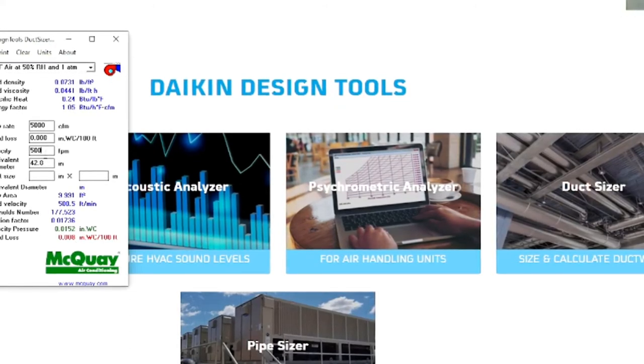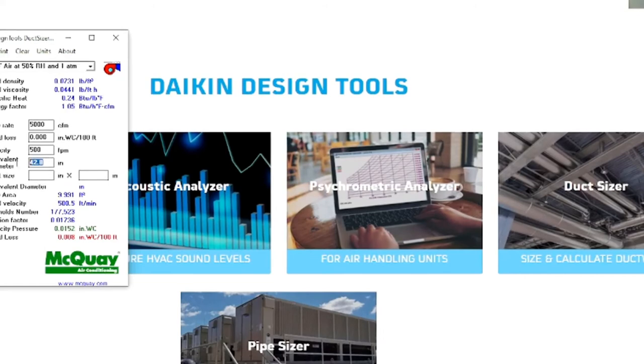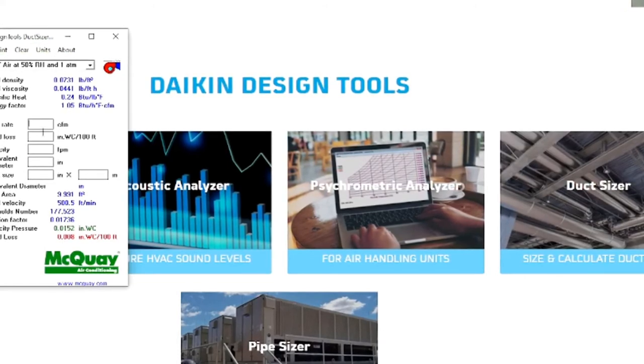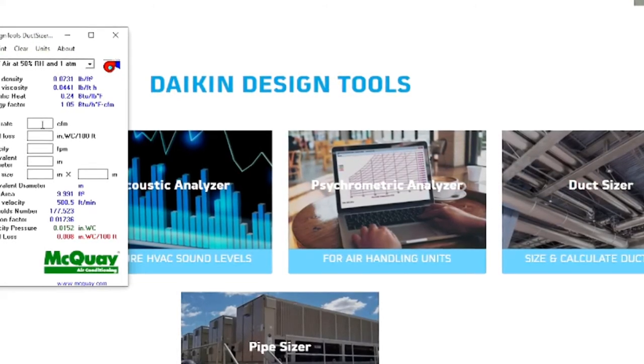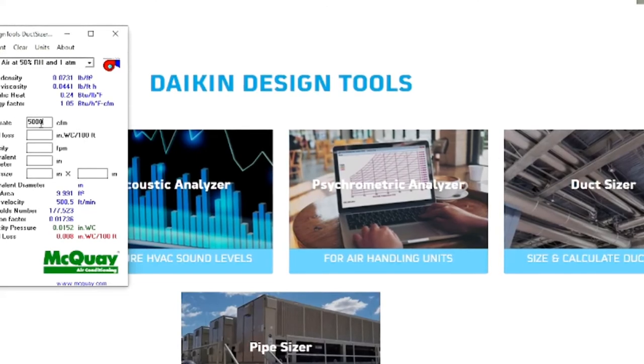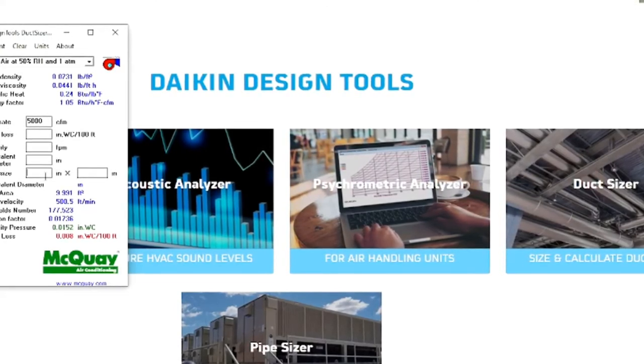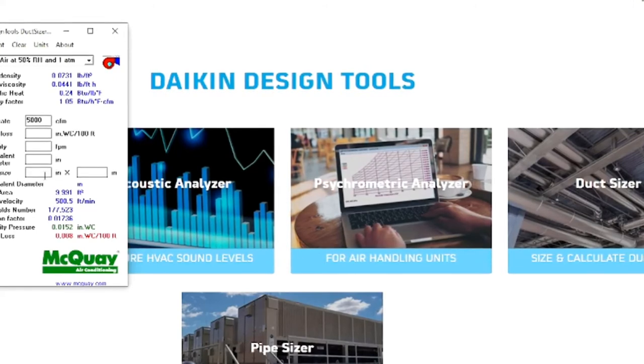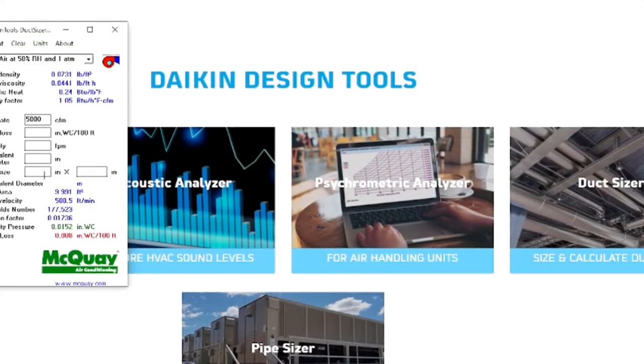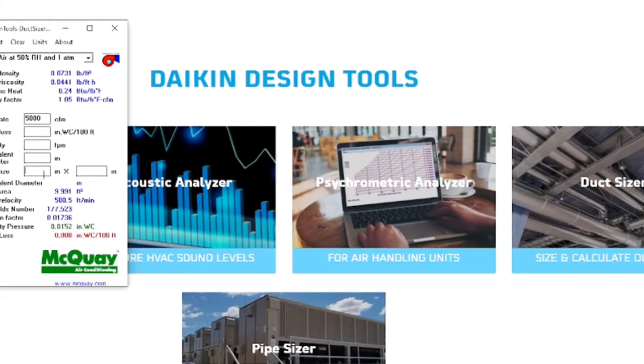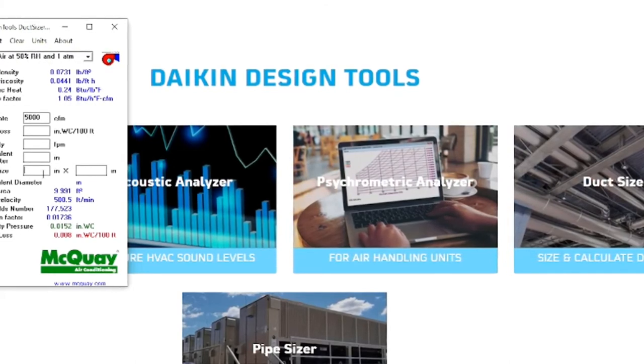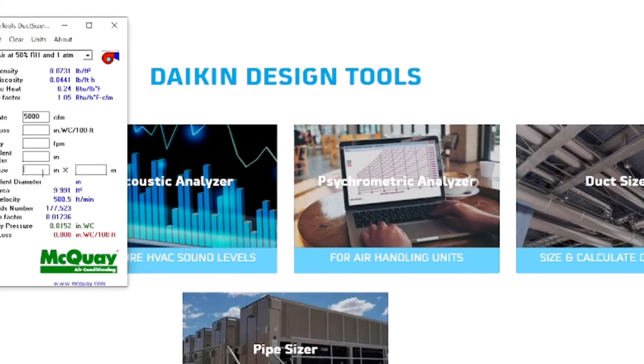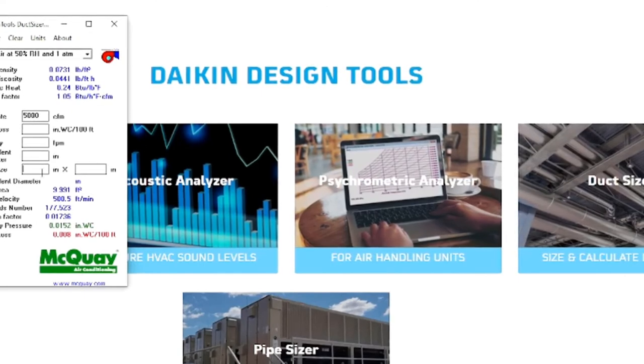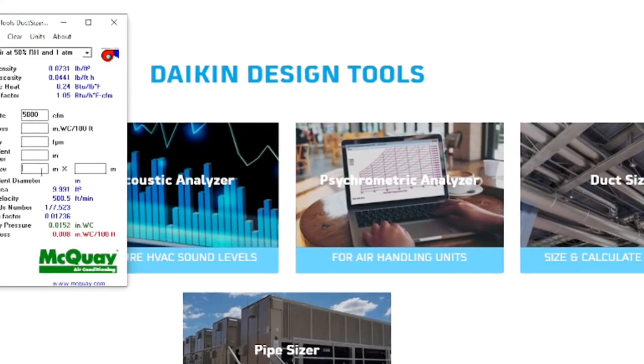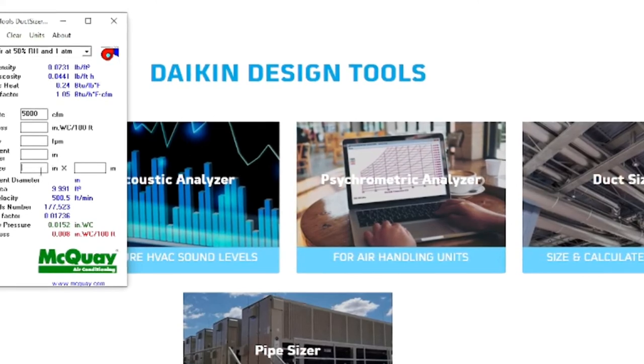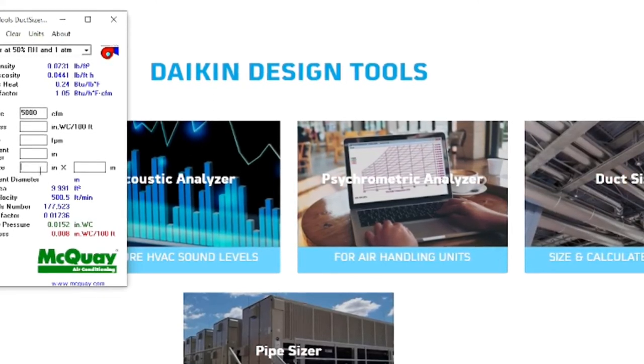So now if I change my ductwork size, I can just go back on the top and put the same number, 5,000, and then on the bottom, I want to put a duct size myself. So when I'm sizing ductwork using the equivalent friction loss method, I want to make sure that my head loss is not beyond 0.008.